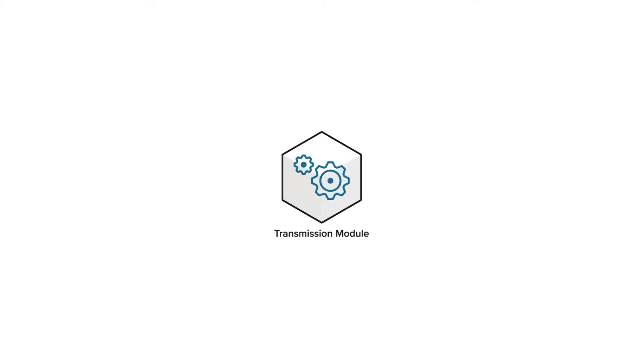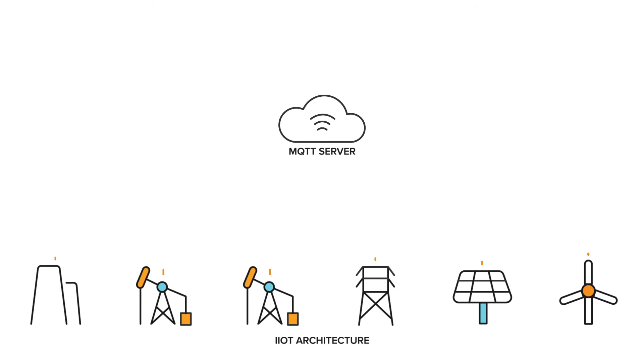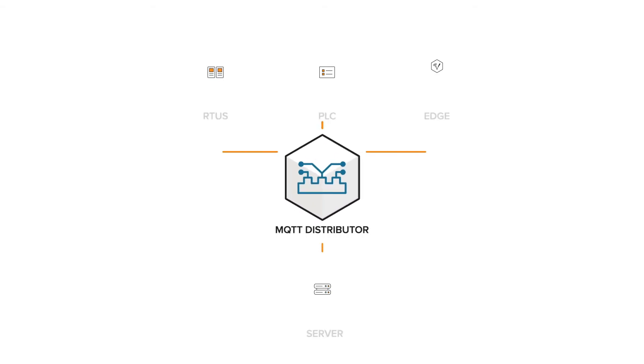For more data, the Ignition MQTT Transmission module can be installed on a server and comes with unlimited connections. Both use Sparkplug and include everything you need to capture and transmit data to a central MQTT server, locally or in the cloud. The MQTT server enables clients to connect, publish, and subscribe to data securely. There are many MQTT servers on the market, and Ignition works with all of them, and even has its own: the MQTT Distributor module.